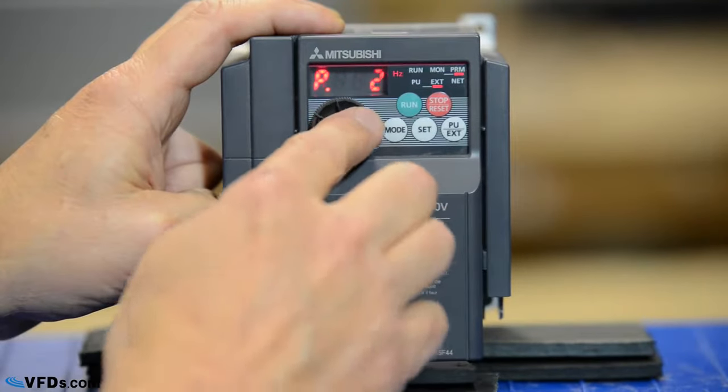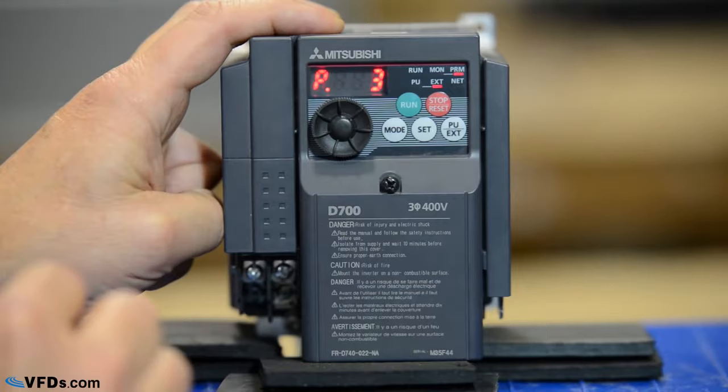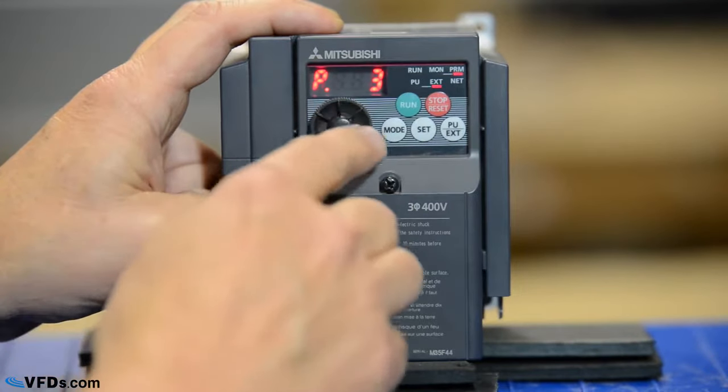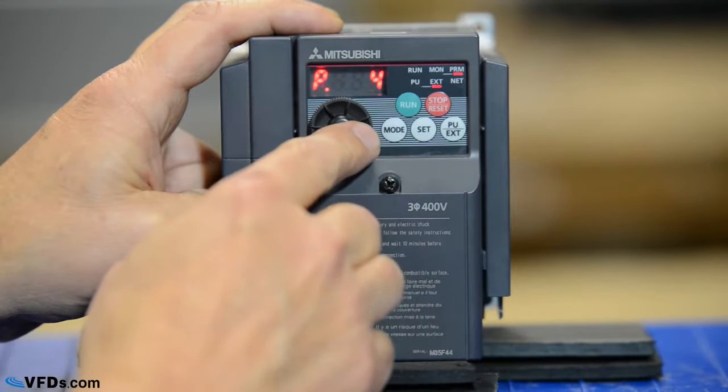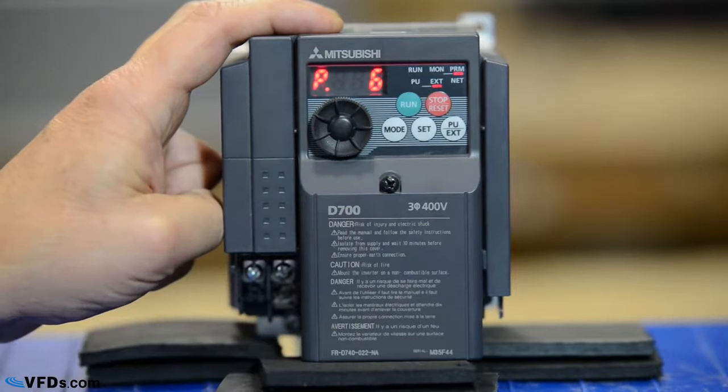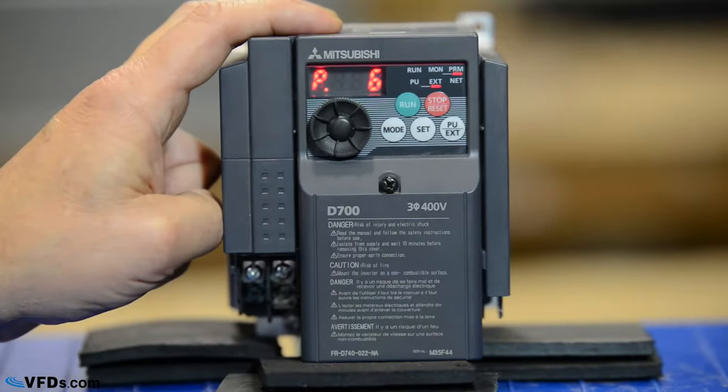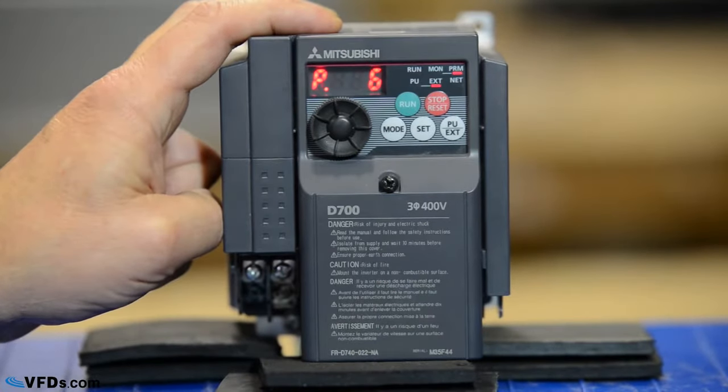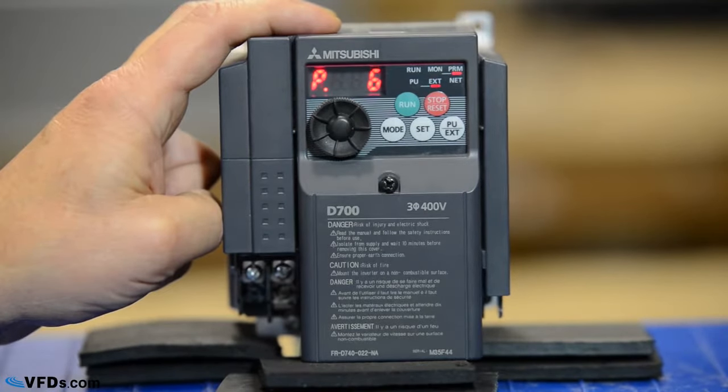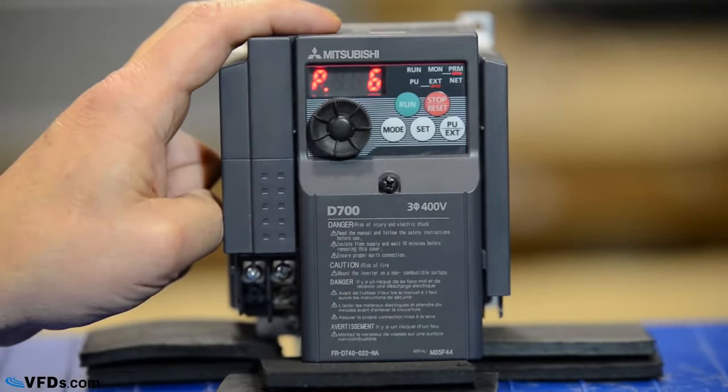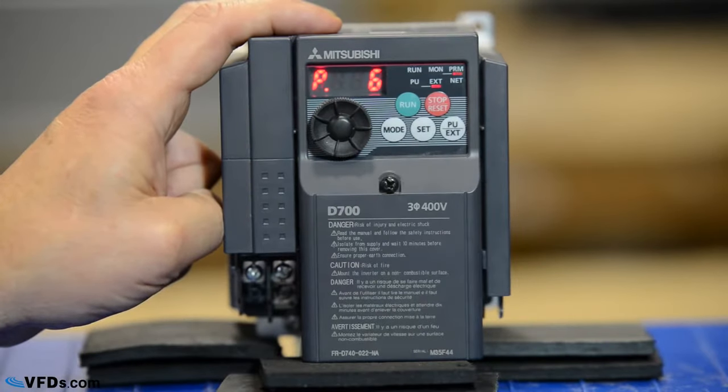I turn the wheel again and we go to parameter 3. That was our motor rated frequency—we've already set that. Here's parameters 4, 5, and 6. Those are preset speeds. If you'd like to run the drive at certain preset speeds, you may want to set one of those. Typically we're going to run the drive on an analog input or through the keypad, so we won't need to set those.